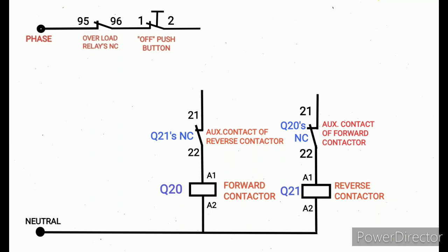Next we're going to draw forward push button. This forward push button is in series with off push button and Q21 NC, with the forward contactor coil supply A1. Next we're going to draw the hold on, because the forward push button is momentary type.